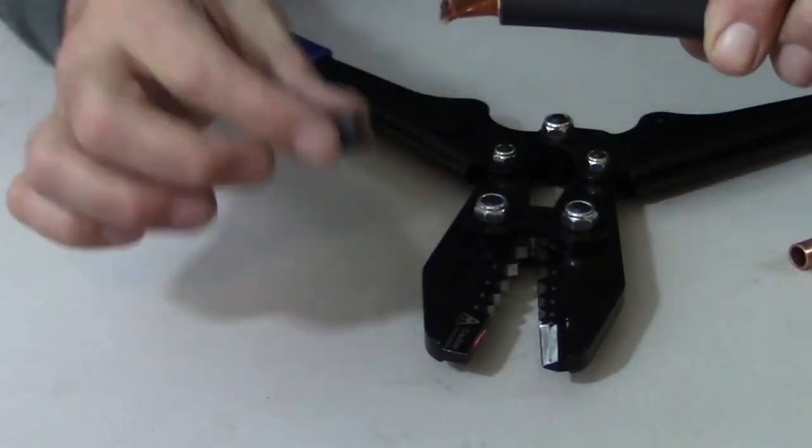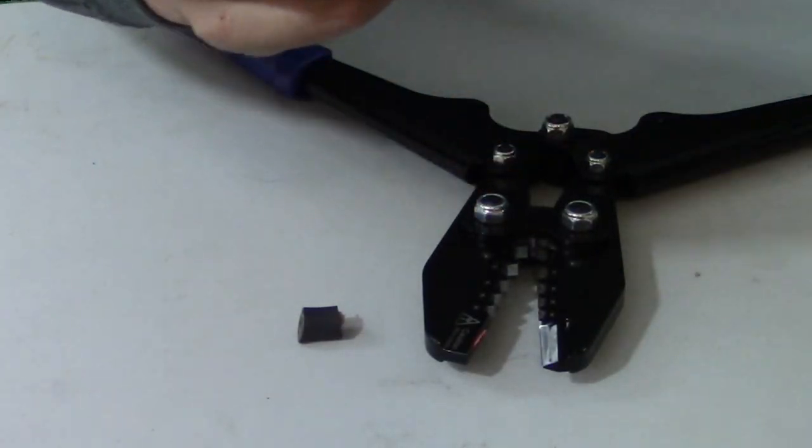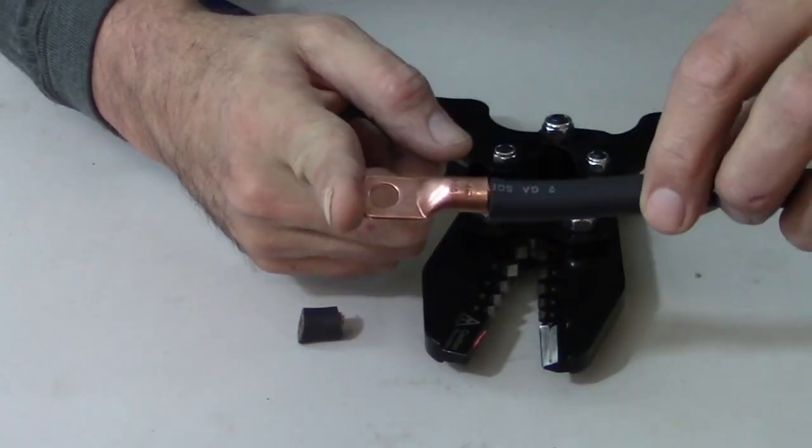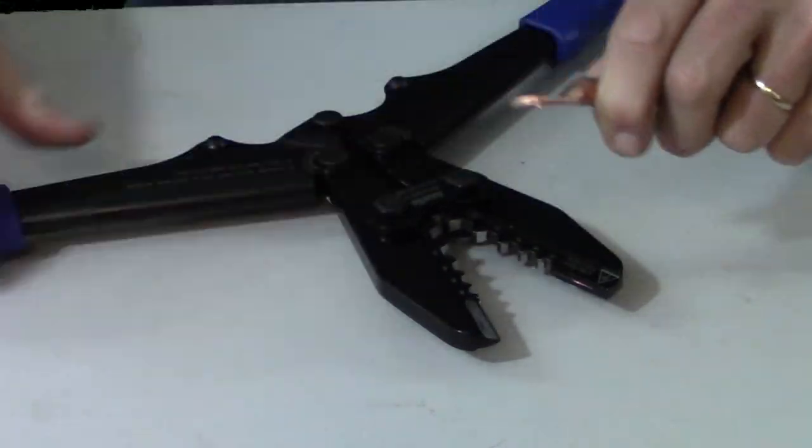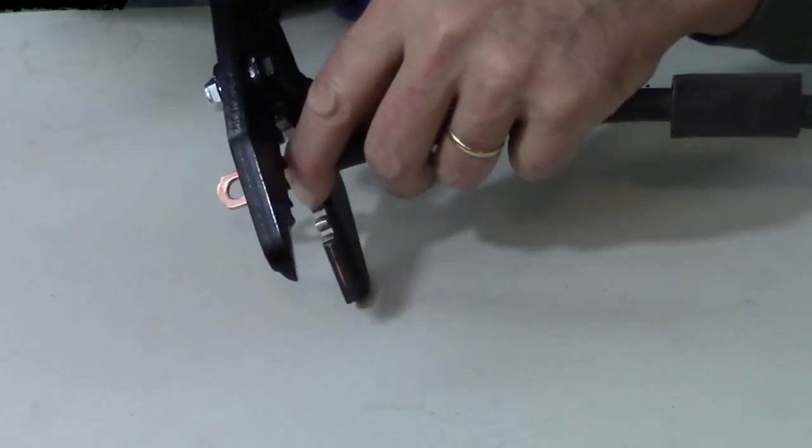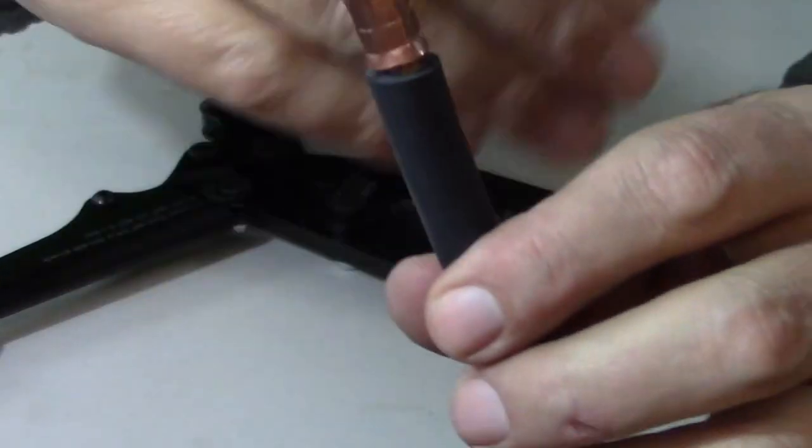Next one I did was the 2 gauge wire. And went ahead and got that stripped, put the lug on. And as I got on the bigger wires, it did actually get easier to crimp. And part of that is because of mechanical advantage. You can see that the larger size lugs, larger size wires, are closer to the pivot point of that crimper. So the mechanical advantage is there.